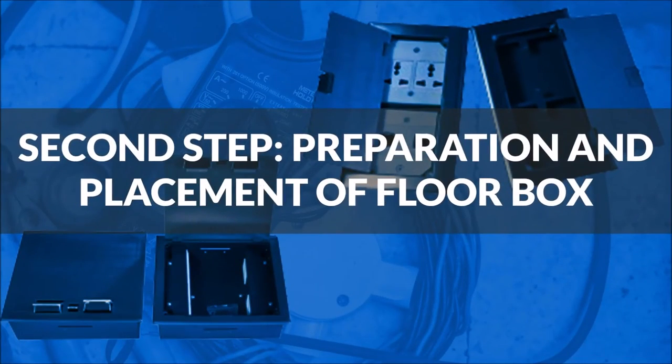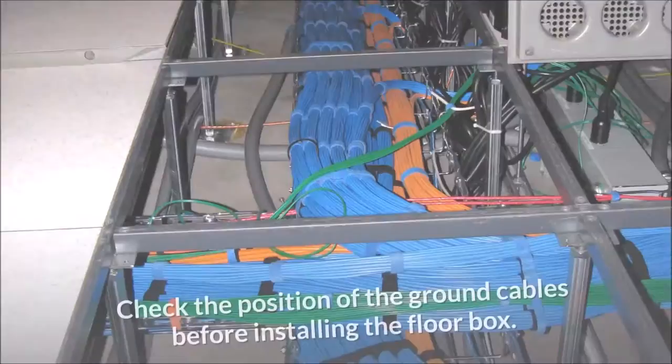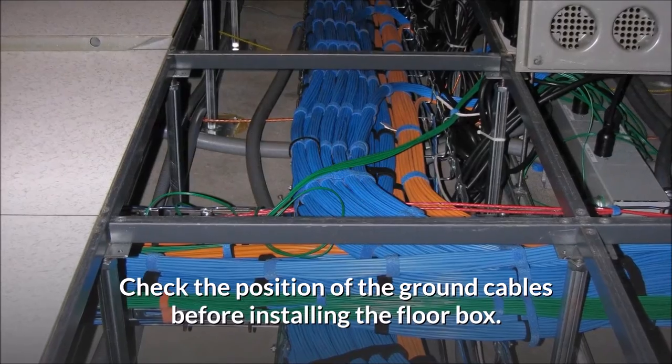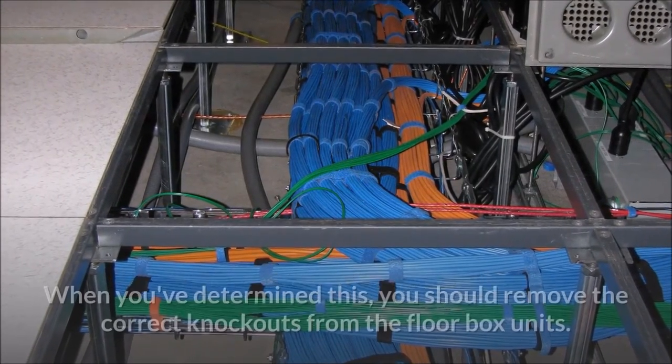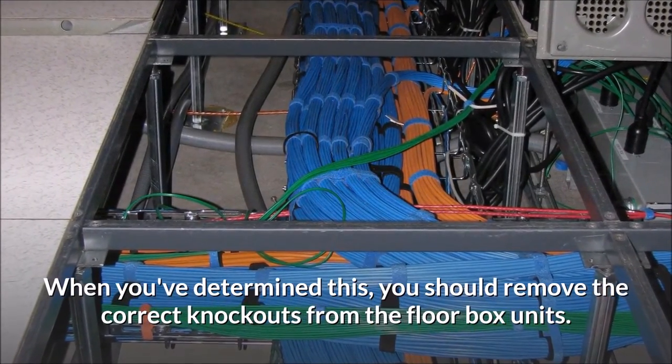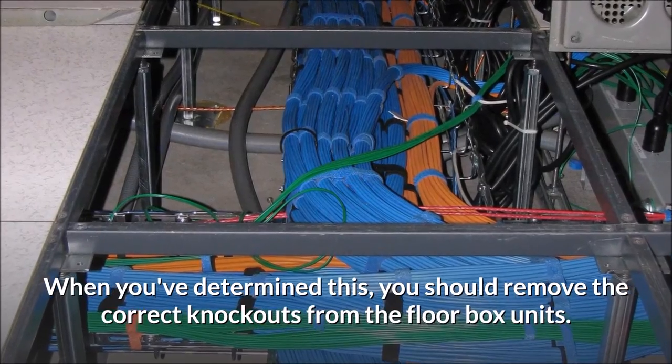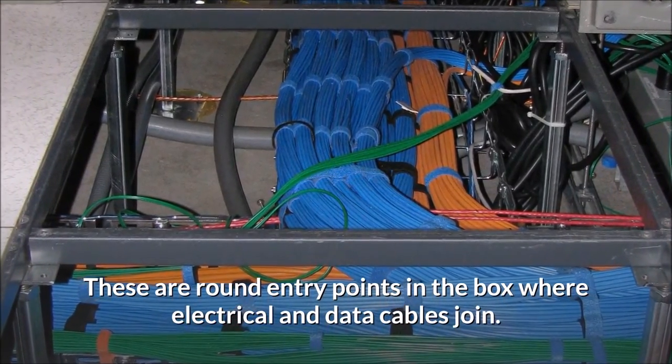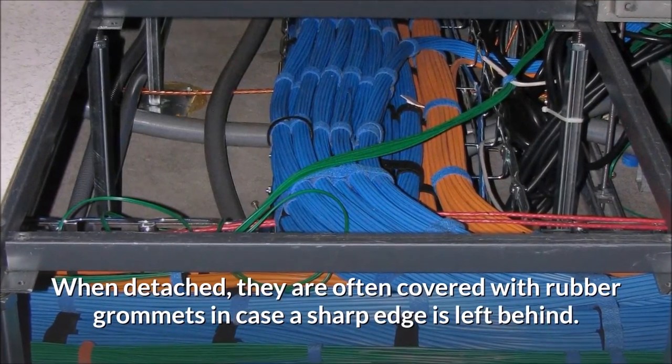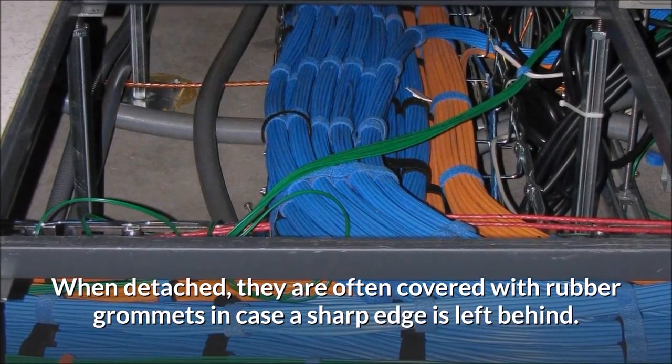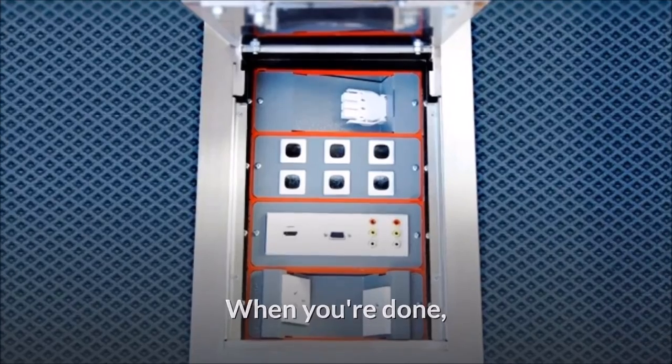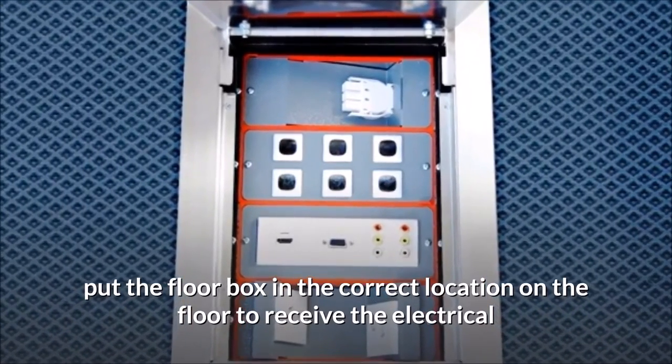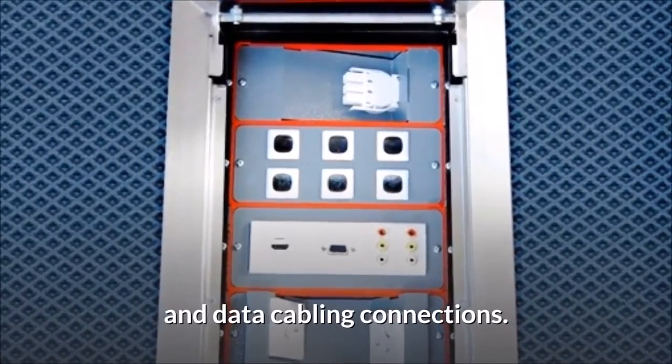Second step, preparation and placement of floor box. Check the position of the ground cables before installing the floor box. When you've determined this, you should remove the correct knockouts from the floor box units. These are round entry points in the box where electrical and data cables join. When detached, they are often covered with rubber grommets in case a sharp edge is left behind. When you're done, put the floor box in the correct location on the floor to receive the electrical and data cabling connections.